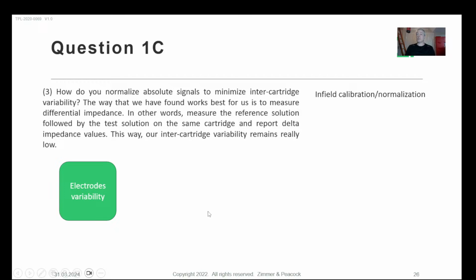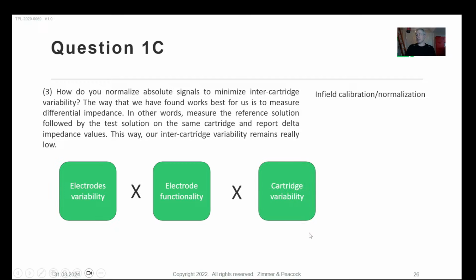So your irreproducibility is due to electrode variability, I suspect, times your electrode functionality. I suspect that you're functionalizing the electrode in some way, and that's a source of variation. Then you've got your cartridge itself, the walls and height of your cartridges, and then your cartridge assembly, the way you put it together, maybe it's not repeatable. All these things stack on top of each other, and you end up with an IVD, an in vitro diagnostic, that's not necessarily repeatable.